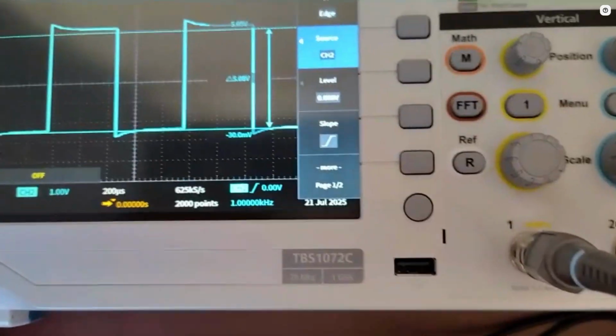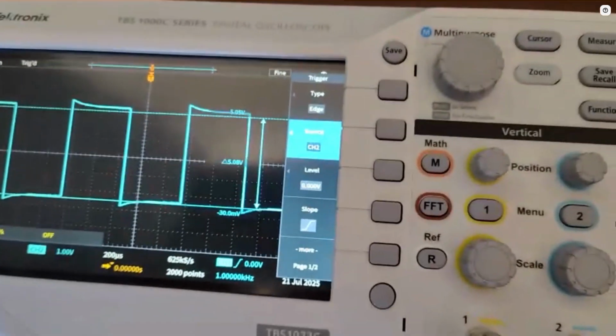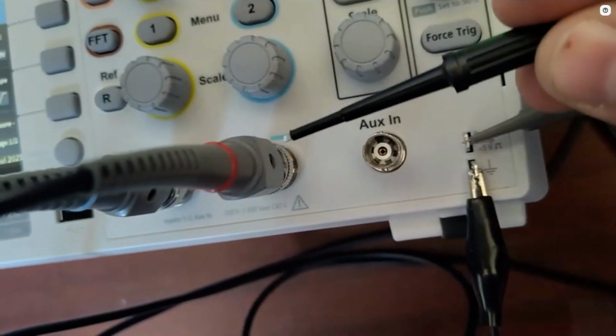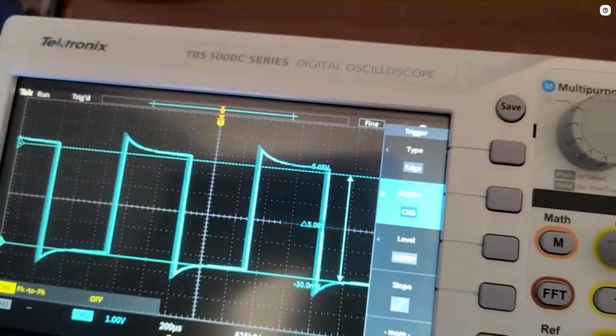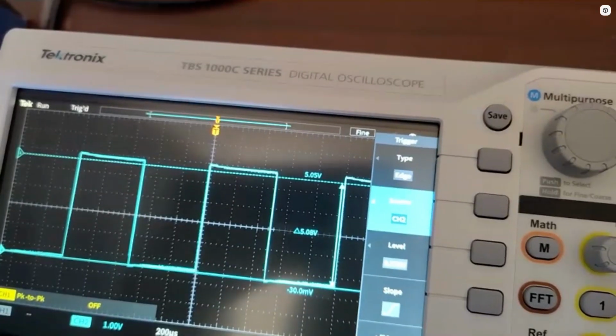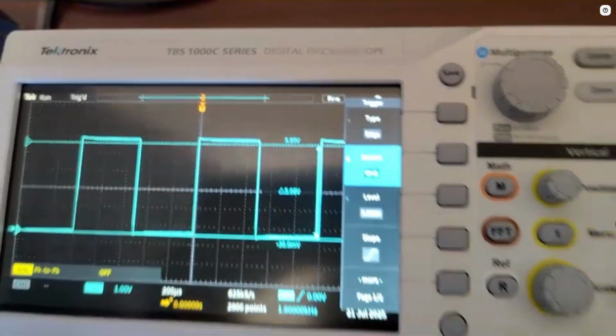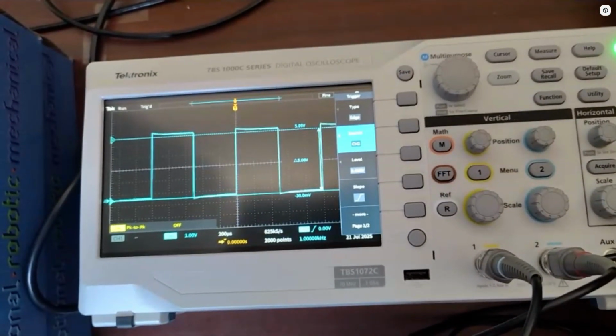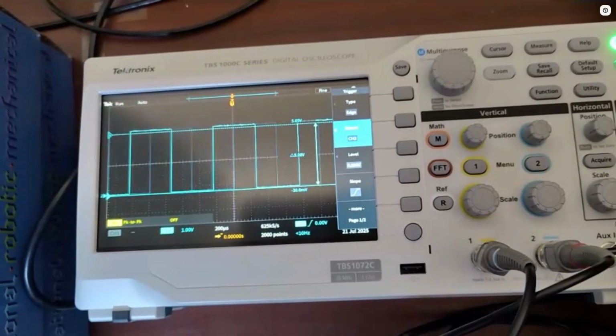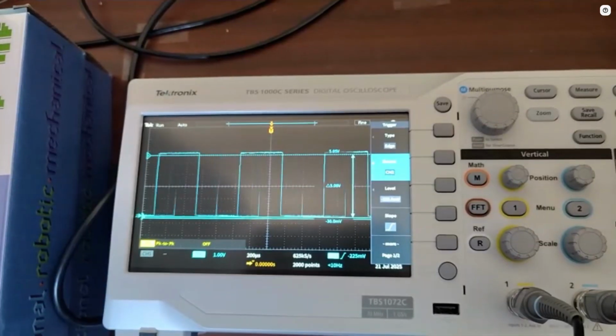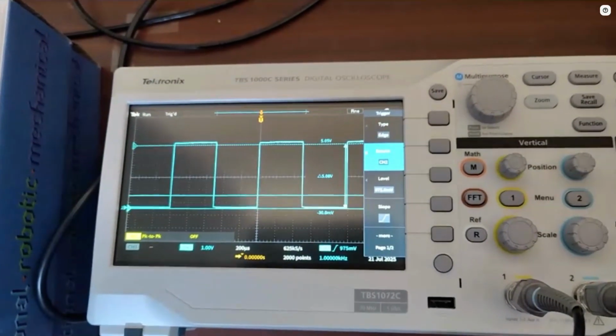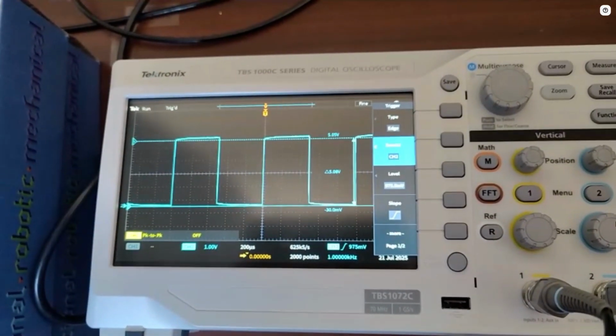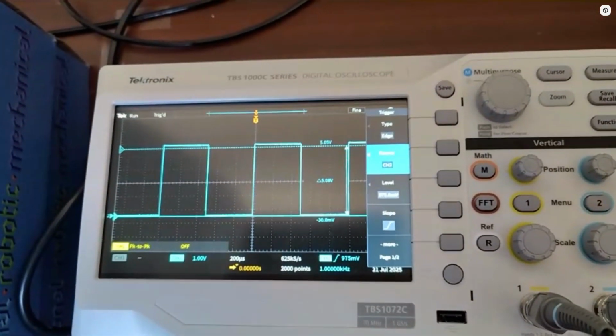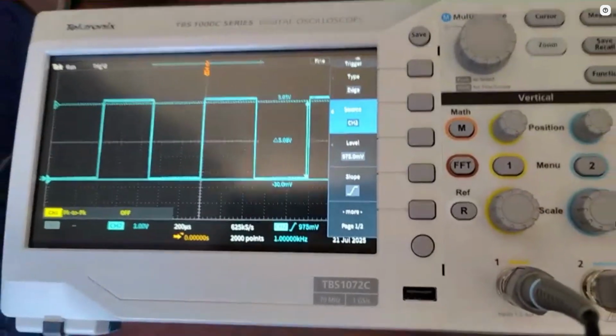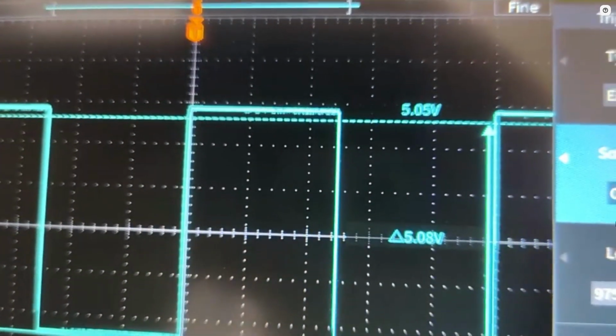And there's my selection. Now, as I'm looking, again, this probe is out of calibration for the scope. So I've got to find my probe, take my adjustment tool, and adjust this until it turns flat. Right about there. Take it out. We're still a little off. Put it back in. I'm going to drop it down just a little bit more. I'm going to adjust my trigger level. As you can see, that line's moving, so now I'm a little bit more stable. I do have a slight blip on the top, but that's okay for what we're after. That actually looks pretty good, and we are generally flat across the entire thing.